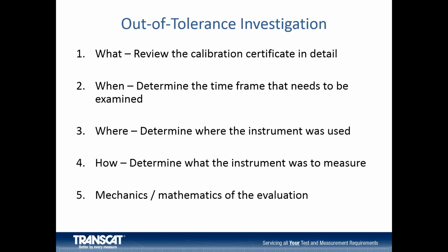All right. So this is all why you're here. The investigation process. The object of the out-of-tolerance investigation process is to identify if there are any at-risk products due to the out-of-tolerance instrument. This process is designed to eliminate products without risk, narrow down your pool of at-risk products if there are any at the end. This is an investigation.